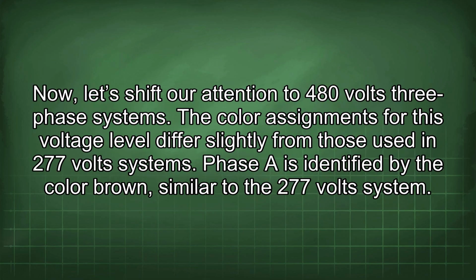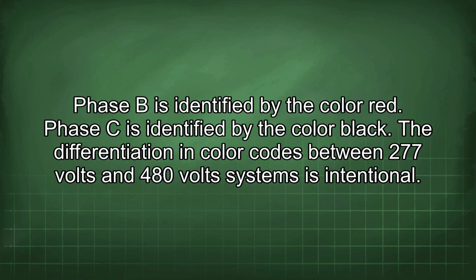Now, let's shift our attention to 480 volts three-phase systems. The color assignments for this voltage level differ slightly from those used in 277 volt systems. Phase A is identified by the color brown, similar to the 277 volt system. Phase B is identified by the color red. Phase C is identified by the color black.